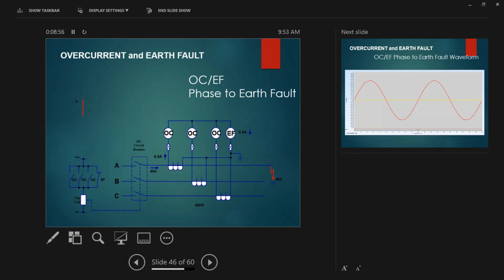Now, earth fault. This is now the scenario of an earth fault. Only one phase. If you inject single phase on the relay, it will see it as an earth fault because there will be no other opposing current in the other legs. So it will go here on this coil and go back here. So it will treat that as an earth fault, which will go first because this is the instantaneous trip. Depends on the magnitude. There's an instantaneous trip as well on phase A, but most of the time this one will go first.